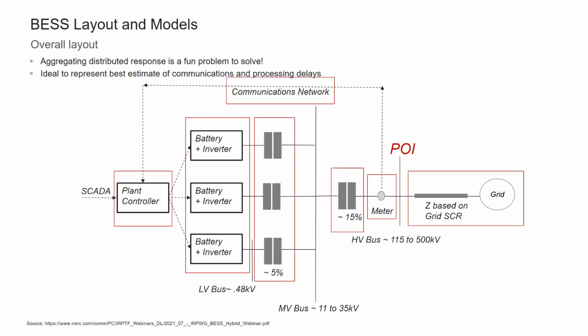Each of these boxes is important, from representing your meter and controller, and to some extent a lot of these inverter-based plants are measurement and controls based, which is one of the fundamental differences from synchronous machines, which are mostly physics based. There is a measurement aspect to the controls of the inverter-based plant, so it's important to represent, to the best estimate, the communication and processing delays, because in some cases they might have an impact.